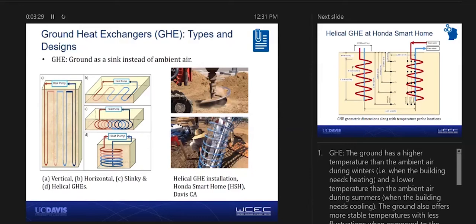Workarounds for these problems are the horizontal GHE and the slinky GHE, but these designs tend to require more land. A compromise between these design constraints is the large diameter, shallow bore helical GHE. The diameter can be anywhere from 1 to 3 feet, and the depth can be anywhere from 12 to 36 feet.